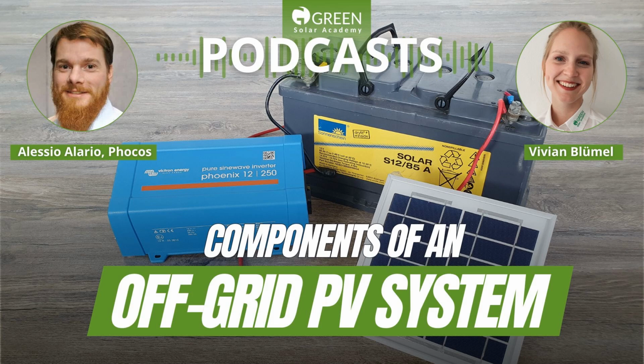That's right. But I think one of the biggest advantages of MPPT is that, essentially, what we've talked about so far is that you can use the incorrect PV modules with the battery, or the cheapest ones in some cases. That's obviously one big advantage of MPPT, that we can do that and still be efficient. So we are not bound to the 60 cell modules. That's right. We're not bound to the 36 and 72 cell modules. Okay, so we can use whatever module we get. Exactly. And we tend to be able to put many modules in series to reach higher voltages, and we have a lot more flexibility in how we configure our PV array.